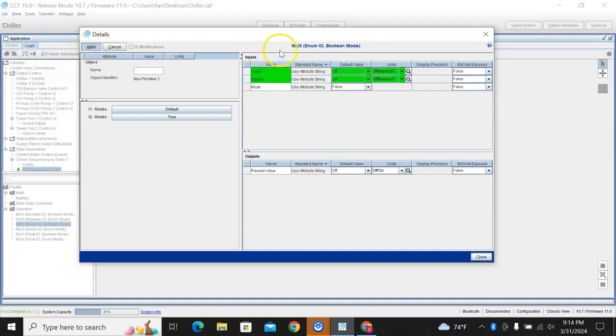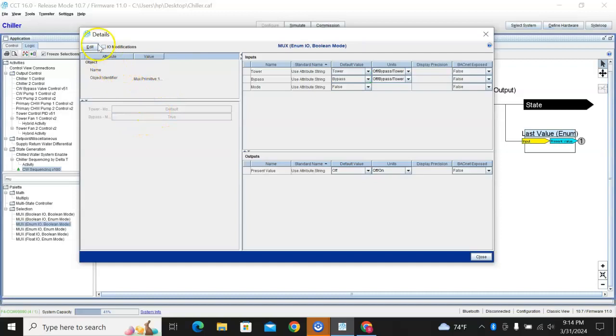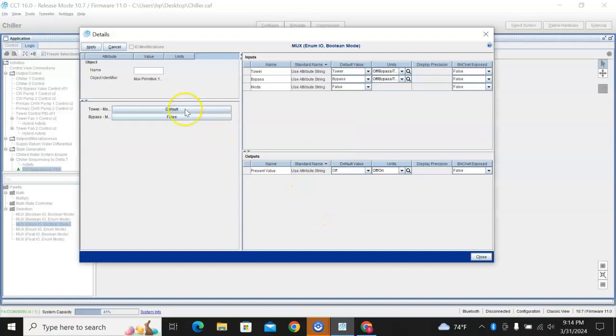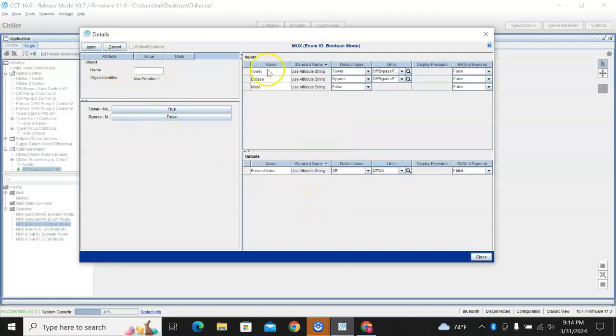Go ahead and apply. So when it's in tower, I want it to go to tower. When it's in bypass, I want it to go bypass. Okay. Same thing over here. When this is false, I want it to go into bypass, and when it's true, I want it to go into tower. Okay? True, false, true, false. I have to do bypass over here, apply.